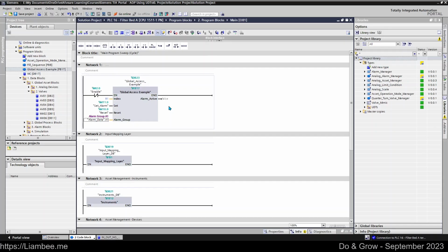You can copy stuff to the library without it being a problem, and it also guarantees that you can use that block somewhere else and not have to worry about the integrity of the project that you're moving this object to, because it's all self-contained, wrapped up in an interface, and the logic is inside the block. And that is the principle. These two lessons that we've just been through make up the core principle of this approach. You have to use the interface and you have to make sure that you're using references.